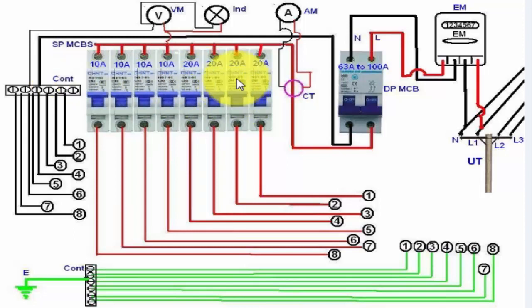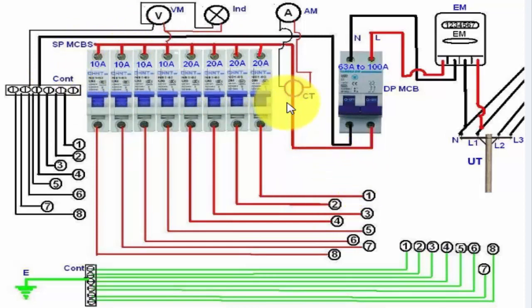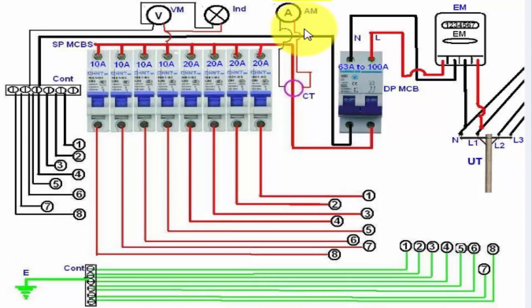Before the connections of the MCB circuit breakers, the phase wire goes through the CT current transformer. The two wires of the current transformer are connected to the ammeter, which will show the total load of our complete distribution board — the total running loads.